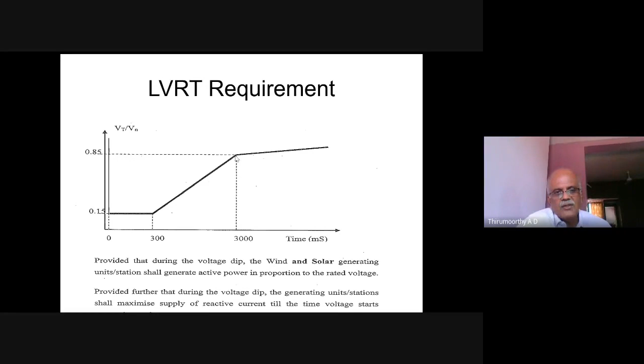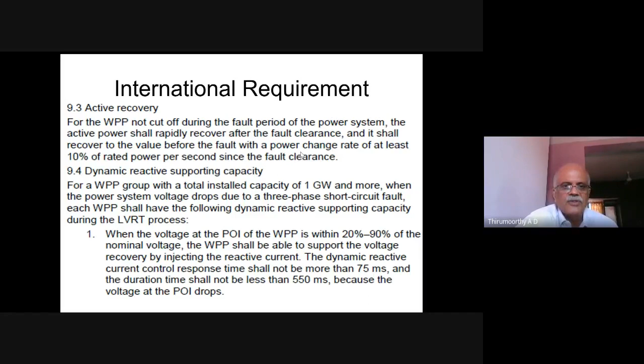Whenever the voltage drops within this region, the windmills should remain in operating mode and regain the original production level. So the international requirement is there for windmills not cutting off during the fault period of the power system. The active power shall rapidly recover after the fault clearance. Most of the other countries have the LVRT phenomenon, but only for the new windmills.